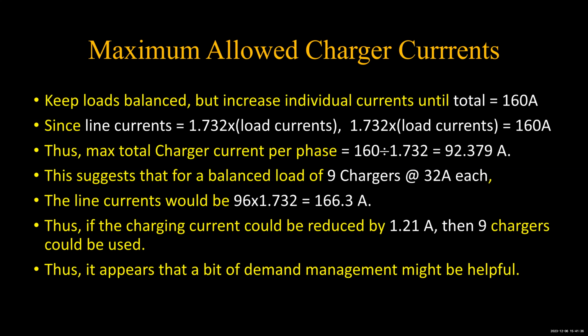Or just go down to the next lower level. If you want to use 9 chargers and you've got the load management capability in the system, then don't charge at 40 amps. Charge at 30, and then you put more chargers in. And if you also have the chargers talking to each other, then you just settle for a little less than 27 miles per kilowatt hour, or 27 miles per hour of charging.